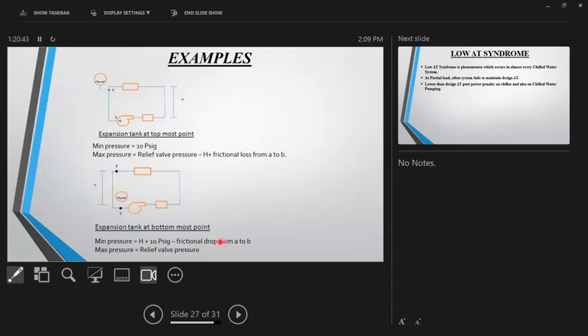And minus friction. This, for the time being, you can keep aside. So in the expansion tank, the minimum pressure at this location can be H, the static height, plus 10 psig. This is the minimum pressure I should have. And for the maximum pressure, you can assume the same pressure over here, that is the relief valve pressure, so PN16. So this is how P1 and P2 are selected. They are a strong function of where the tank is located. Is this clear?